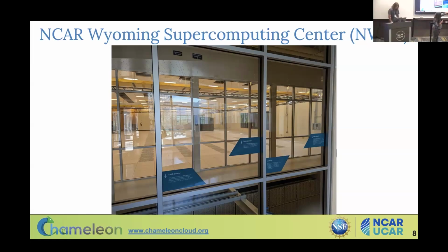And then there's filters down here, as you see. That's our raised floor underneath. And then there are fans that will pull the air back under the floor and then let it go back up. And there are chilling pipes in between those filters and the fans that will chill it if it needs to be chilled. But often we do all evaporative chilling, which is nice. And we don't run our chillers. We do have big, huge chillers, but we rarely turn them on, which is lovely. We just let the natural evaporative cooling do the work. And that's why we get such a good PUE value. Next slide.